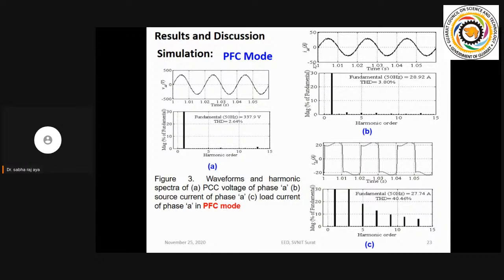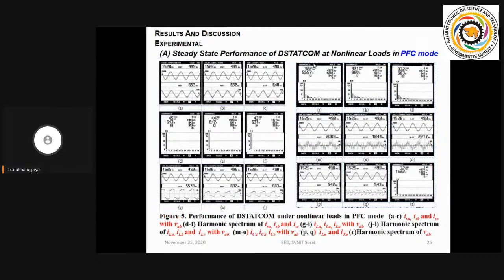Next point is, you can see here, this is the demonstration of the waveforms during PFC mode. You can see after compensation how much we have, less than 5% distortion. But the main objective is distortion, also neutral current you can see. P and Q you can see. In these two figures, one is the load neutral, second one is the supply transformer neutral. Both are equal and opposite.